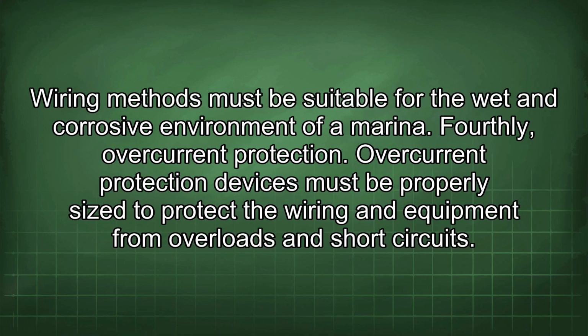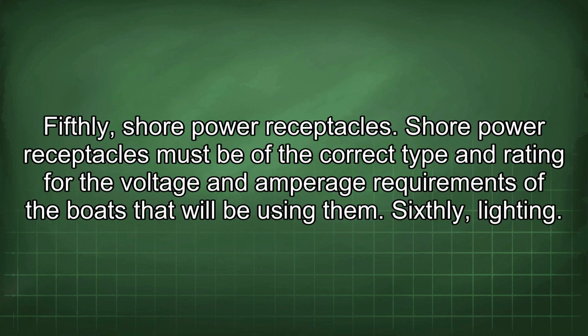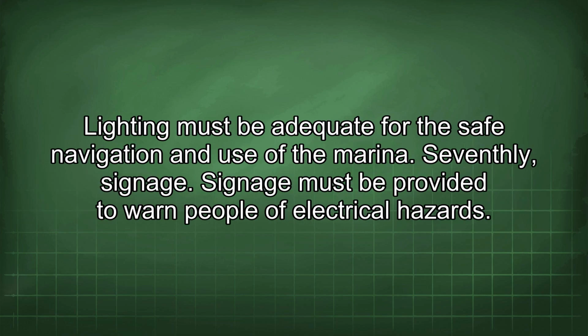Wiring methods must be suitable for the wet and corrosive environment of a marina. Fourthly, overcurrent protection. Overcurrent protection devices must be properly sized to protect the wiring and equipment from overloads and short circuits. Fifthly, shore power receptacles. Shore power receptacles must be of the correct type and rating for the voltage and amperage requirements of the boats that will be using them. Sixthly, lighting. Lighting must be adequate for the safe navigation and use of the marina. Seventhly, signage. Signage must be provided to warn people of electrical hazards.